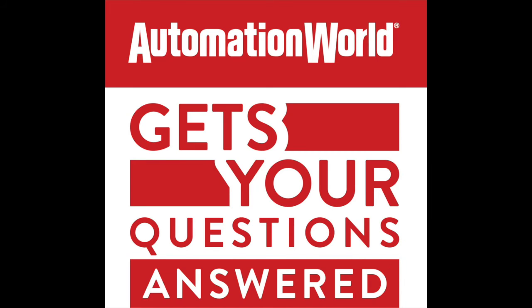Sure. And since we kind of led with high temperature environments, let's start with that. So high temperature, just how hot is it? Again, that's going to tell us which product to best use. And then the other thing to consider is maintenance issues. So, for example, with an air conditioner, you may have maintenance on filter changes, or you might have something that is dealing with condensation, and dumping water bottles, for example. So it's important if you can get a solution that eliminates that type of maintenance. Air to water heat exchanger, for example, once you mount this to the enclosure and you've got your cold water supply, very little maintenance whatsoever. So you're saving that on the back end.